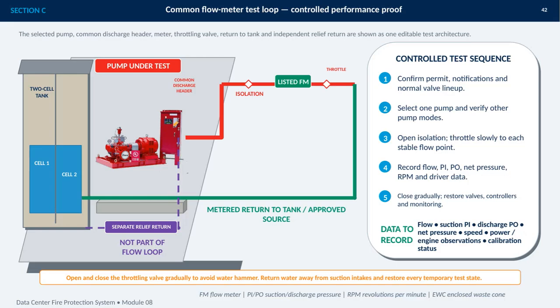This slide presents the common flow meter test loop used to demonstrate controlled pump performance. Water is drawn from the two-cell tank, passes through the pump under test, moves into the common discharge header, and then through the listed FM flow meter and throttling valve. The metered flow returns to the tank or to another approved source. The separate relief return is not part of the flow loop, and it must remain independently routed.